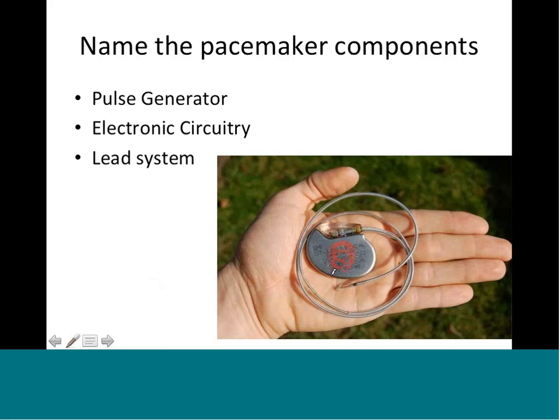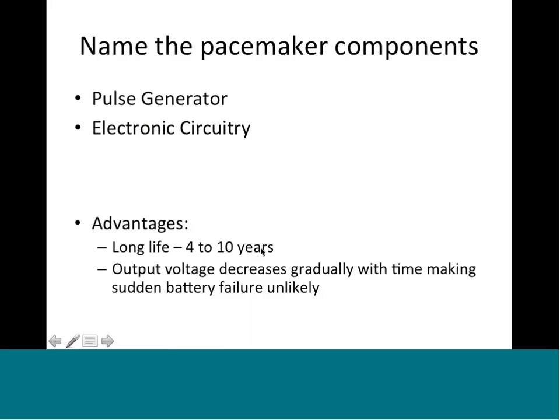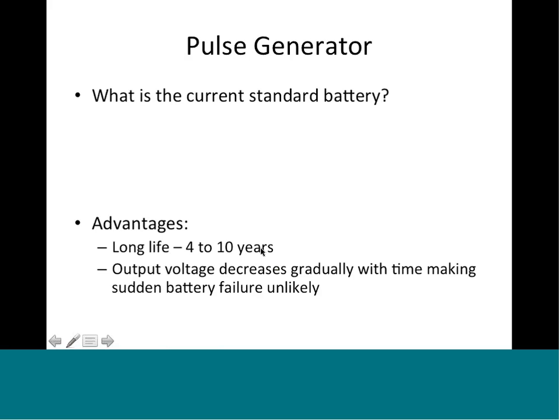So this is your pulse generator here. Then you've got your electronic circuitry, and connected to that, this thing is your lead. So the main thing is your pulse generator and then your lead - those would be the components of the pacemaker.